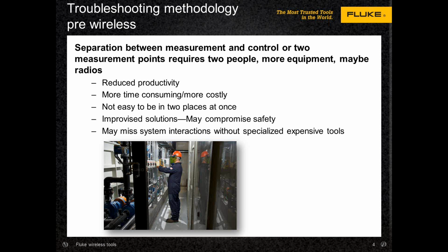I mean, not everything. If you're talking about making measurements in an electrical panel, there's some similarity there, but the size of the panel may have an impact on what you're doing, the energy level that's present, and just exactly what you're doing all play into it. Right, and if it's cause and effect, maybe you want to flip a switch and then go over to a motor that starts, but maybe there's a delay on the motor. You want to check multiple places on that circuit. Or if you want to do live-dead-live testing on a branch circuit off of a panel, it's easy to do with the wireless tools because they help solve that separation issue.